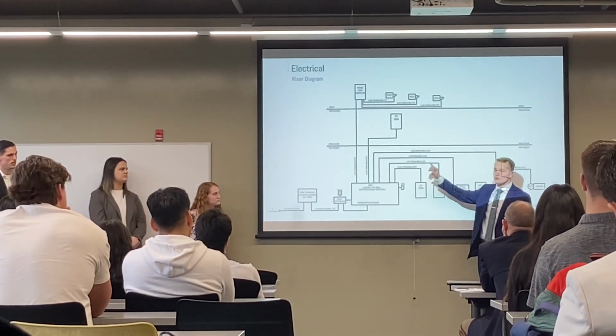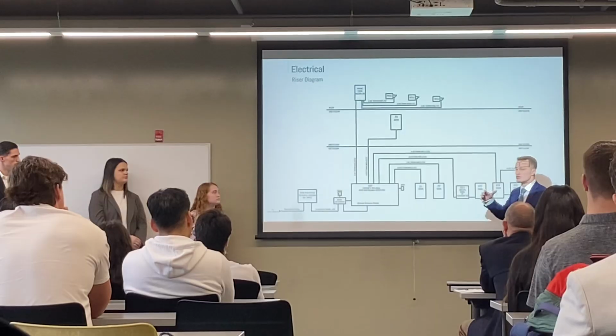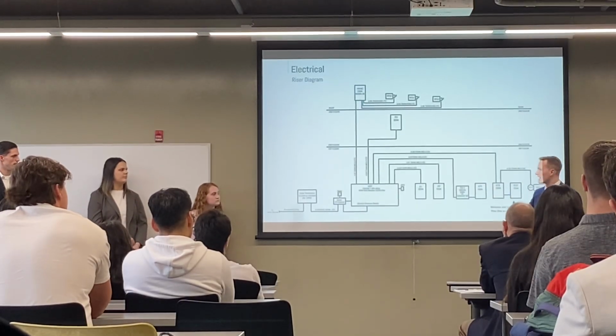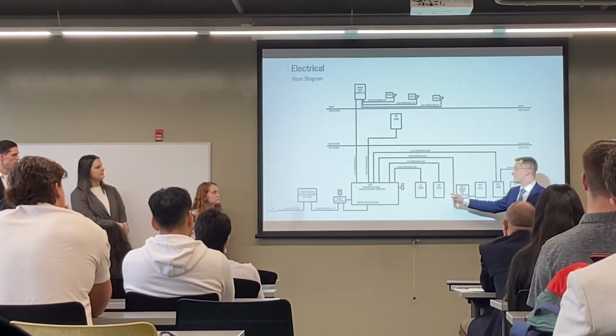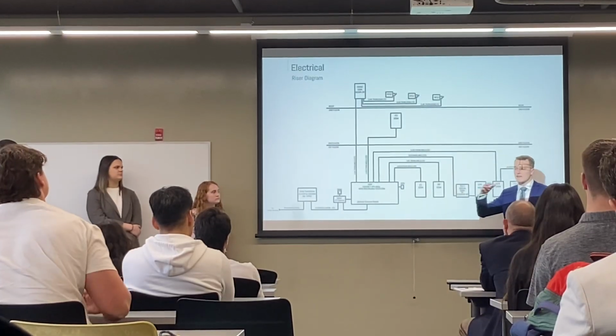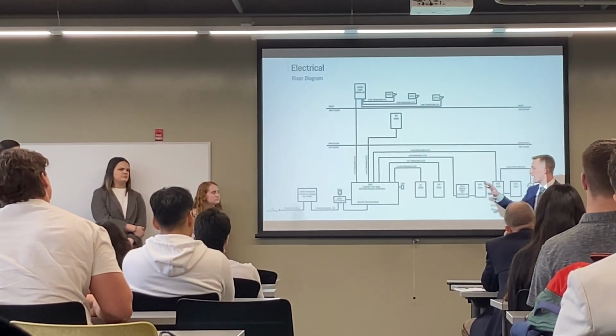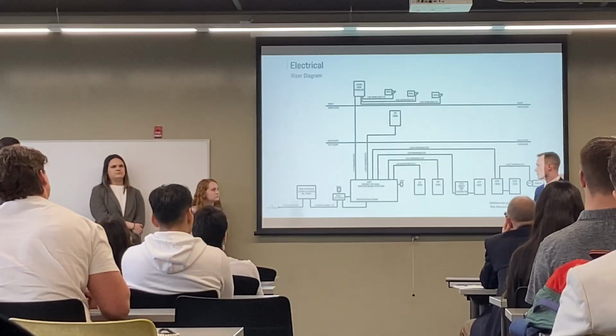So P1 and P2 kind of handle the bulk of the load, so that's like the general receptacles, the lighting, kind of the bulk of the load of the building. Then we have a dedicated AV panel because the equipment is pretty noise sensitive, and so everything on there will have isolated grounds to help prevent that.